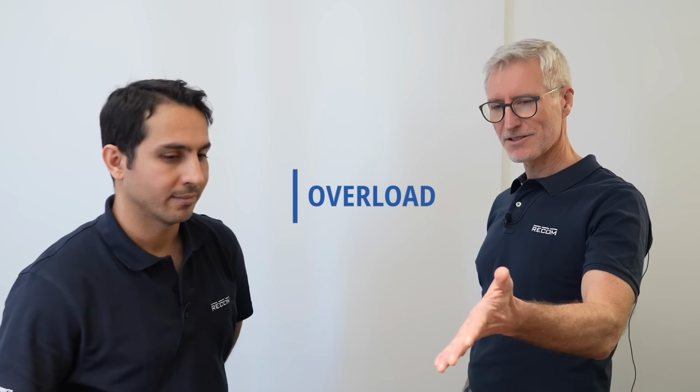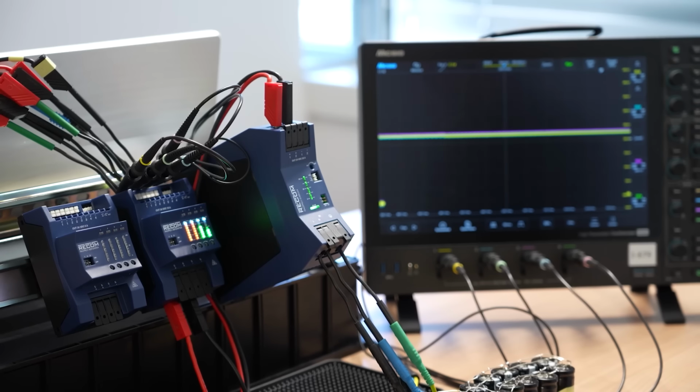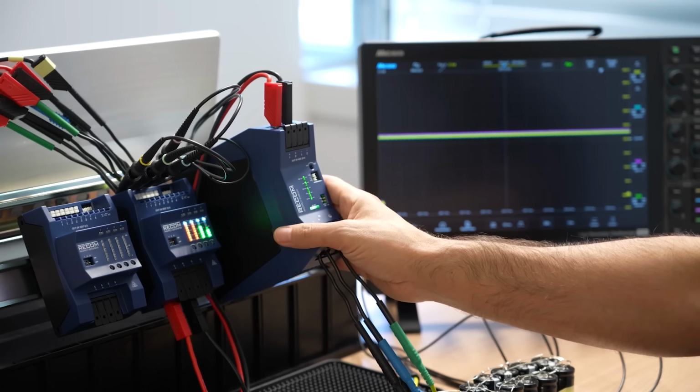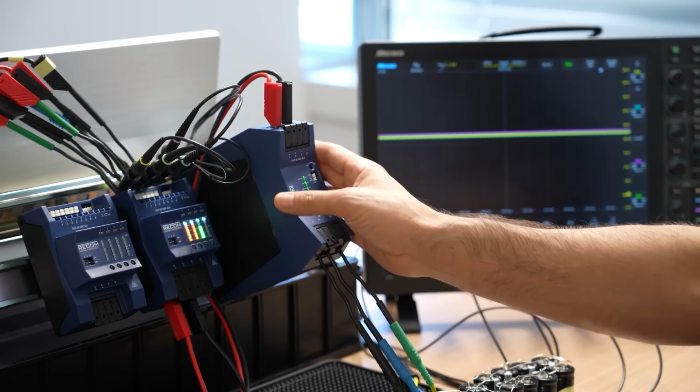So Moss, can you show us the situation when the power supply is not properly selected? Let's say the power supply is undersized and one of the channels gets an additional loading, which would drive the power supply into overload. Yeah, sure. So channel 1 and 2 are fully loaded and channel 3 half loaded, and after a while, which is 5 seconds, because this unit has a boost power.